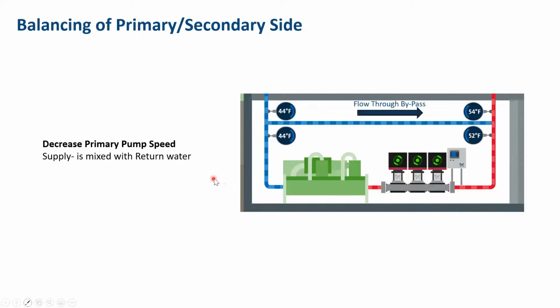The second scenario is if we're starting to see supply water mixing with our return water. So we're flowing supply chilled water back across the bypass into the return. At this point, our building is shutting down. Everything is being satisfied, and we're not requiring the flow we need, and we're starting to push some of that flow back to the return side. And then we'd see that represented in this temperature, and therefore we would know to slow our pumps down.